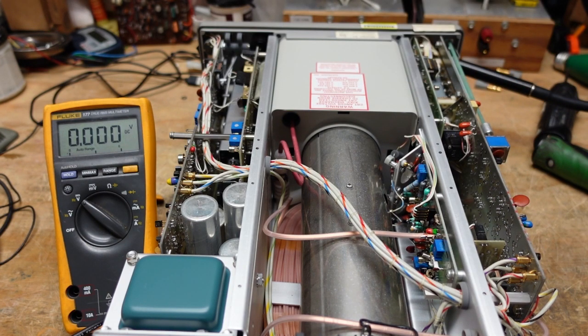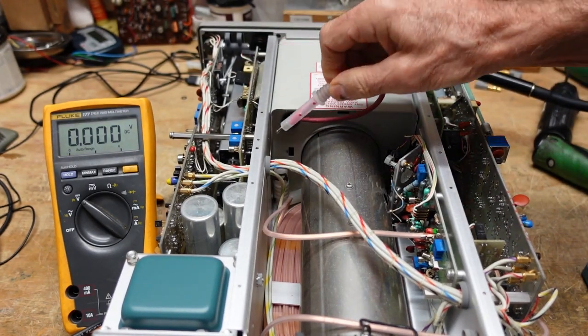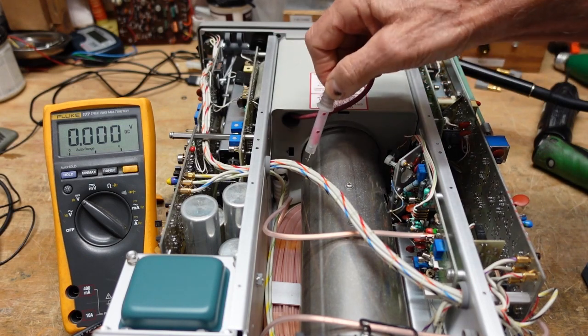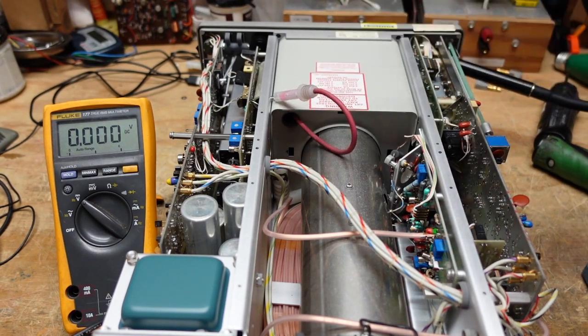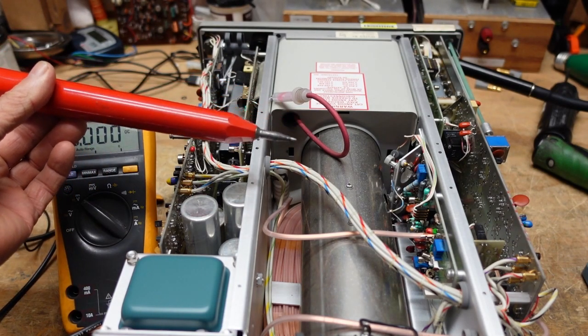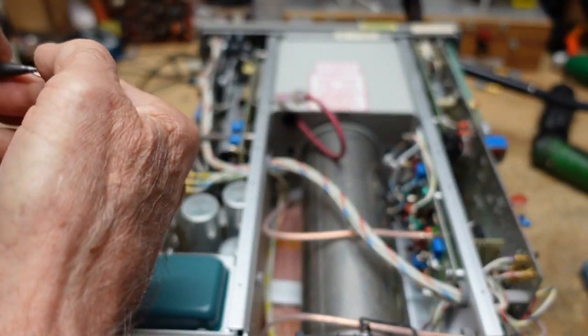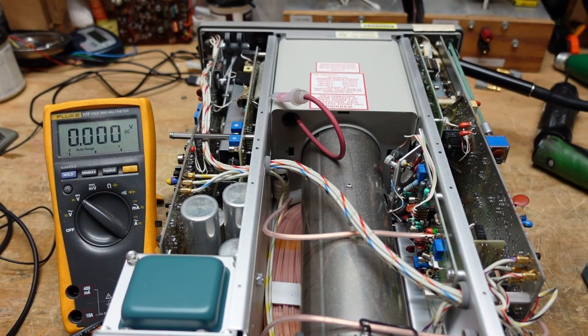We need to make sure that when we disconnect the high voltage anode that we discharge the tube. We're going to just discharge it right to the case here because we don't like getting shocked. It can be hazardous to your health and well-being. So we just pull the connector out and ground it right to here. Well I think you saw a spark, so yeah, it's been grounded out now. The high voltage comes from down in there, and I believe at one point I had an extender for that which I no longer have, so I'm just going to put a piece of wire on here and insulate it so it doesn't arc, because high voltage likes to arc.